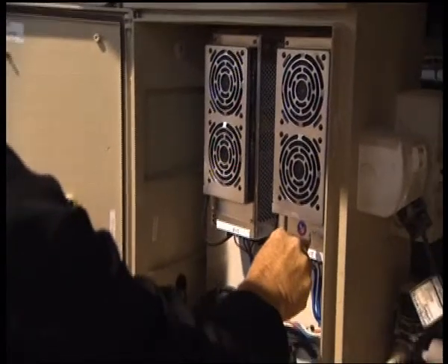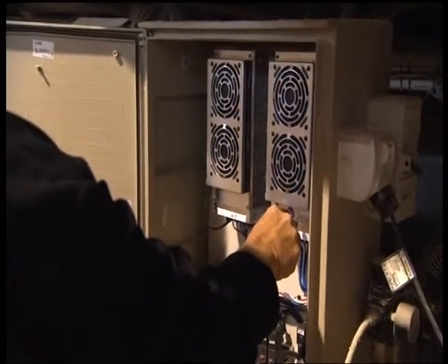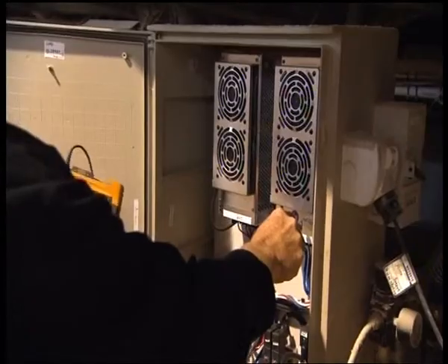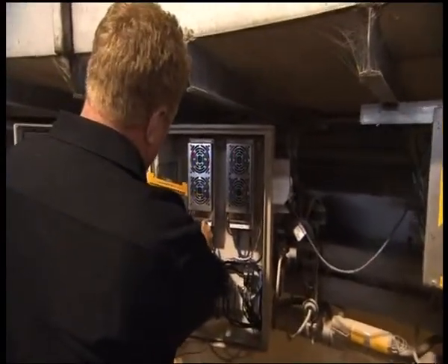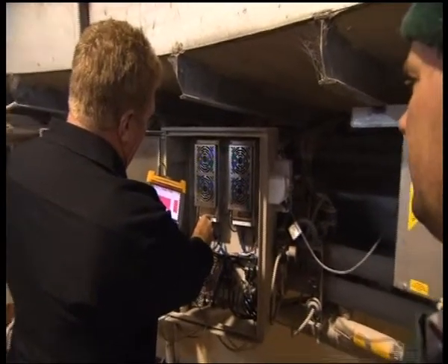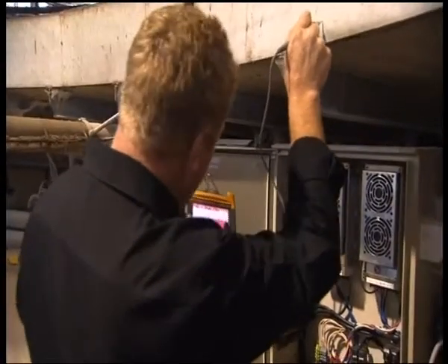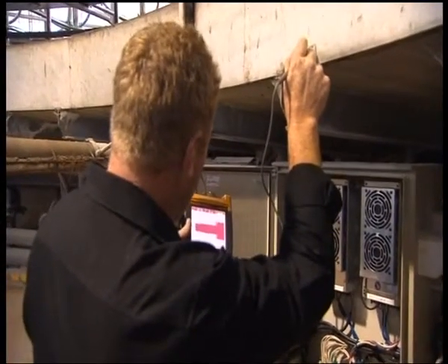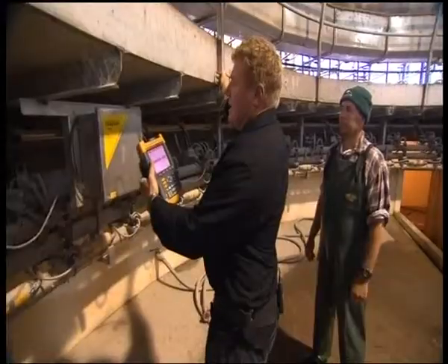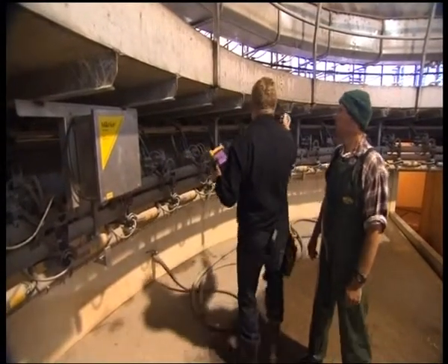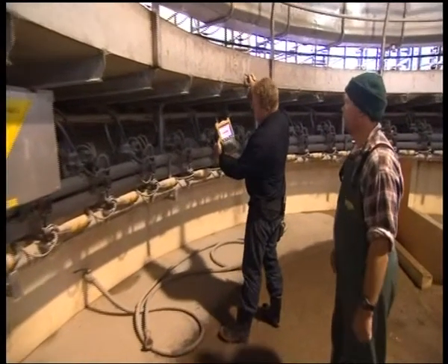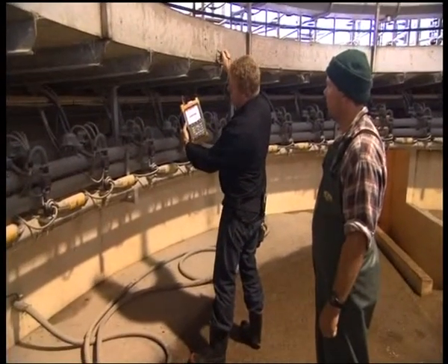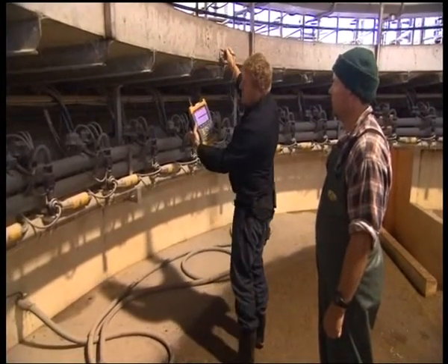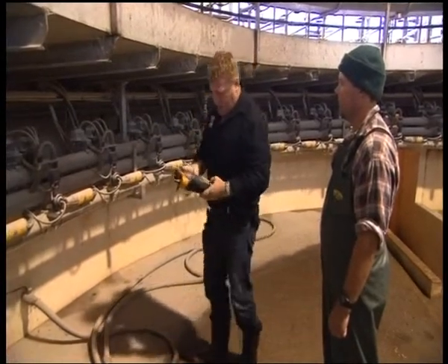The equipment to look for in relation to these harmonic voltages are any form of switch mode power supply, which could be your pulsator power supplies or any of the automated equipment power supplies. And they need to be well filtered, and then variable speed drives are the obvious one. They do it not only in their rectification of the voltage, but also when they're putting out the voltage to the variable speed motors. We go around, and we get right around here, and we're finally back to where it should be, back at 61 millivolts. So it's quite easy to fix, and fairly cheap to do.